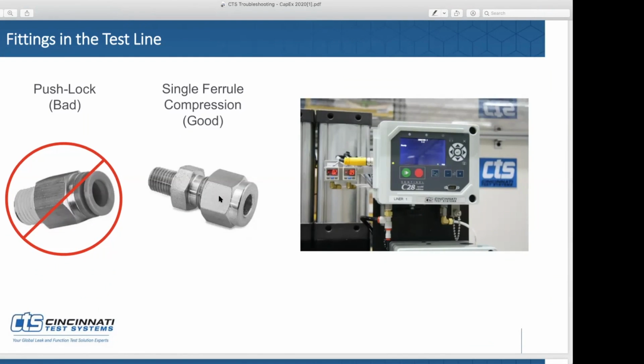Oh, yeah. So fittings. Everyone loves push lock fittings. They're so easy to use, and great for maintenance: remove your hose, throw it away, start with a new one. The biggest problem we find with push lock fittings is their repeatability over time. It's an O-ring that has a tube that fits into it, and eventually that tube will either wear or have scribe marks from debris, causing leaks. And the O-ring compression may have some issues. Our suggestion: never use push lock fittings on your test lines. Use them on your pressure coming to your test instrument, but on the test line side, use a compression ferrule style fitting. That will give you a positive lock on your tubing.